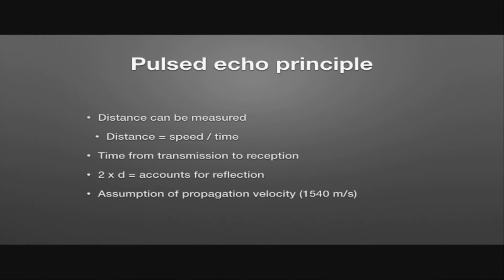Pulsed ultrasound is also important for determining the depth of a structure being imaged, which is obviously extremely important in ultrasound. This is known as the pulse echo principle. If I send out an ultrasound pulse and assume the velocity of ultrasound through tissue is 1,540 meters per second, I can calculate the time it takes from when I send out that pulse for it to be reflected off a structure and received back. Knowing that time and that speed, I can work out the distance travelled using distance equals speed times time.